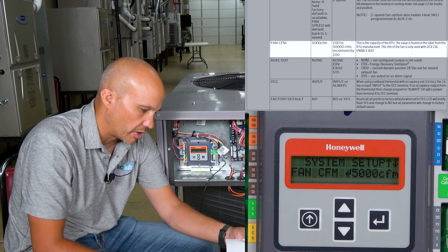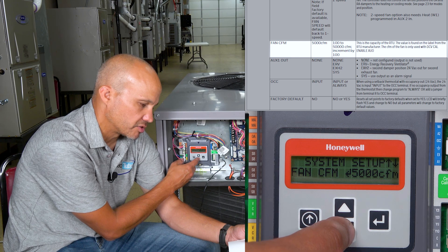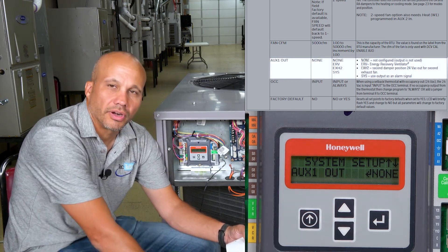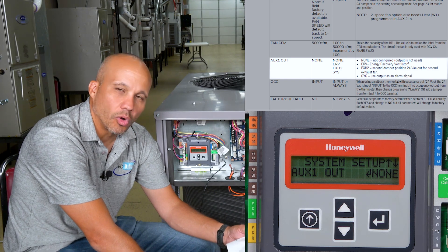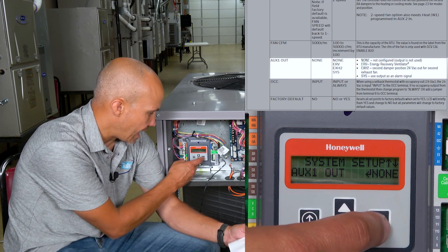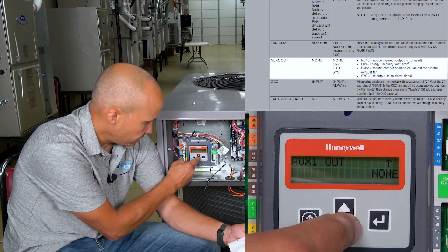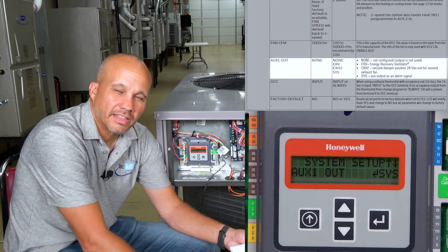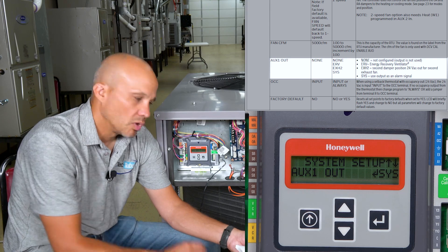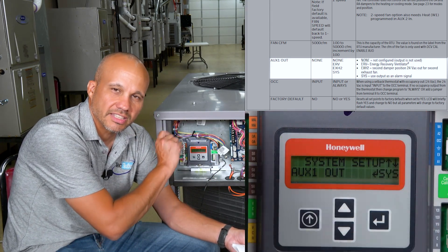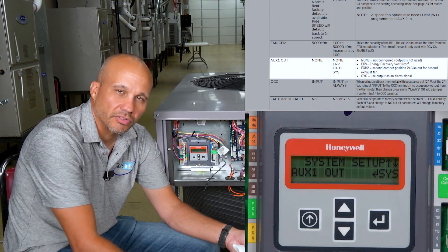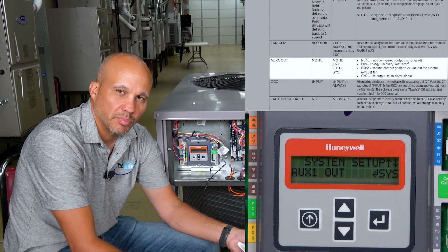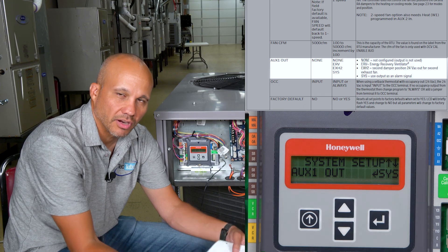CFM doesn't really do anything for most applications — 99.9% of the time it's a useless field, so don't worry about it. Aux 1 Output: there are different things you can program it to, but almost every single time you'll put it on SYS — hit Enter, scroll to SYS, and hit Enter to save. That's a system alarm: whenever there's an alarm with the economizer control, it gets sent out on that auxiliary output as a contact closure, and your thermostat, BAS, or whatever can pick that up and know there's a problem on the roof.